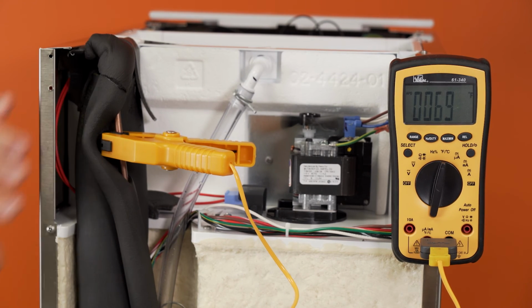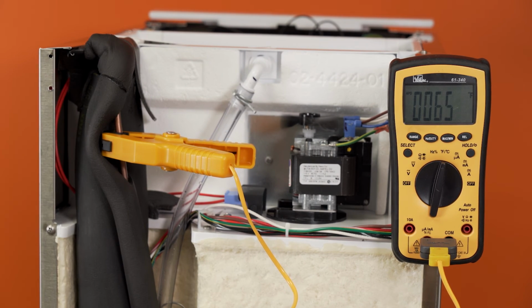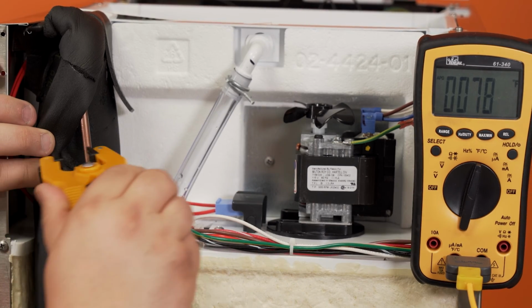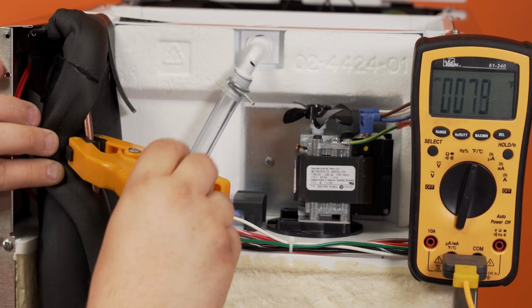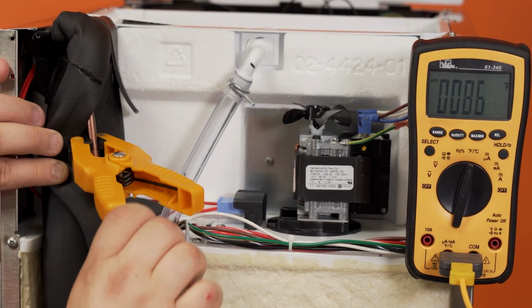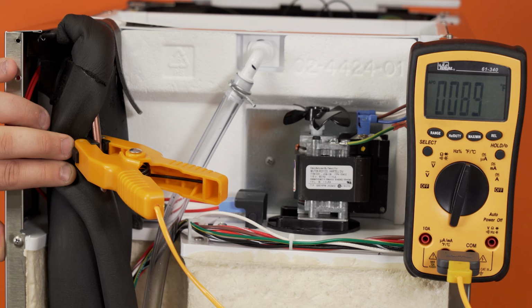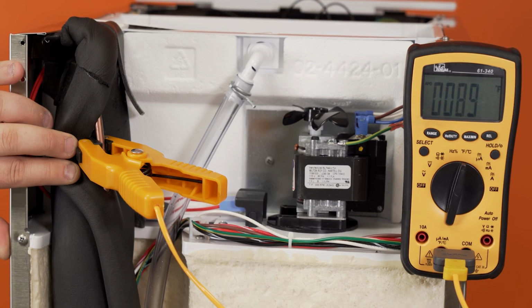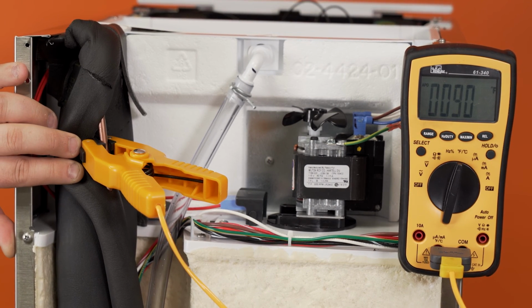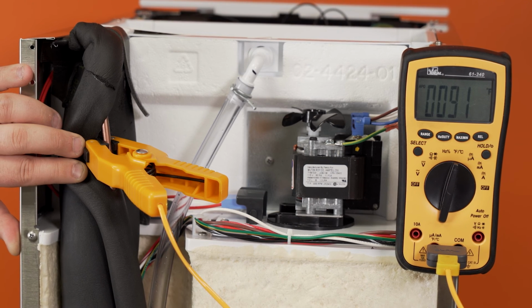With the temperature probe or clamp, take a temperature reading on both sides of the hot gas valve. A properly functioning valve should be closed during the freeze cycle and should have a temperature change of 5 degrees or more. If minimal or no temperature drop across the valve is detected, this would indicate the valve is not closing completely and should be replaced.